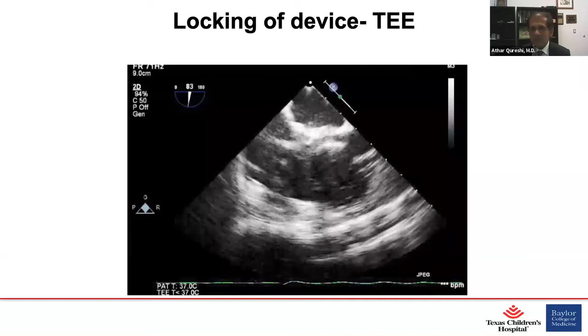So if you are happy that you have grabbed the rims, don't be alarmed by this image. In fact, go ahead and lock the device. The nice thing about this device is it can still be retrieved with the safety cord. If for some reason we were actually wrong and we had not grabbed the rims, or there was a shift in the device when we locked the device, it can safely be retrieved through the delivery catheter with the retrieval cord. So again, this is just a nice image showing extreme shift once you've locked the device. And again, it has actually shifted into a much more favorable position after the device was locked.